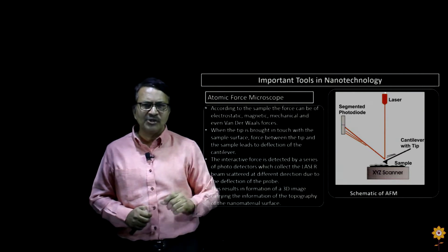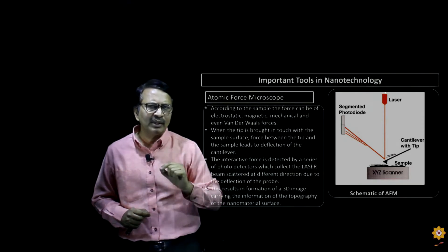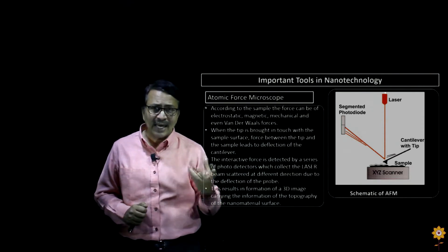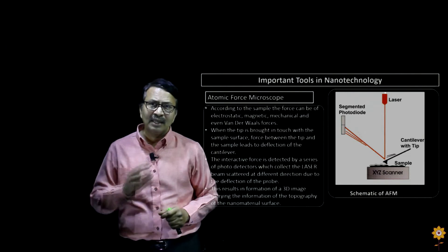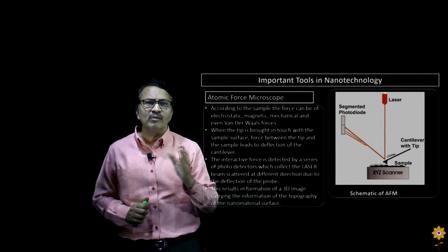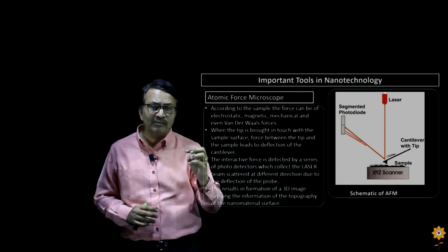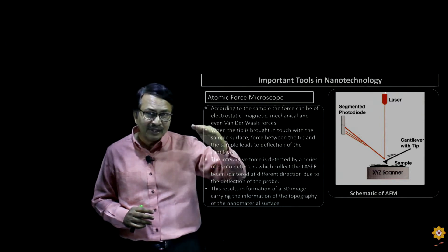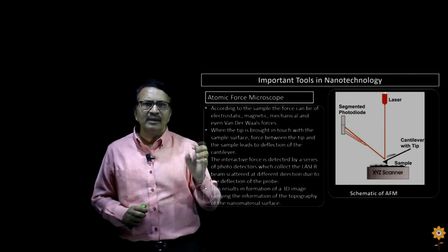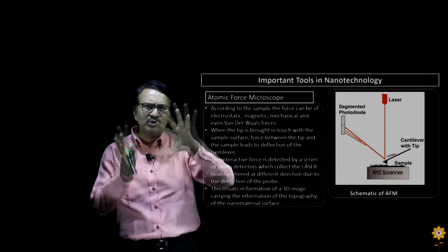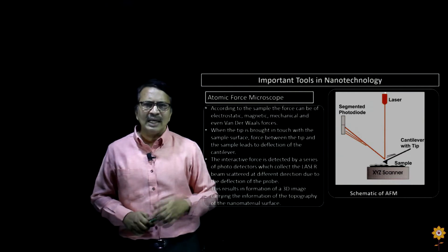One important thing to mention here: the interactive forces that exist between the sample and the tip of the cantilever. These interactive forces can be electrostatic, magnetic, mechanical, or Van der Waals forces. Depending upon the quantity of these forces, the deflection of the cantilever will change accordingly. This deflection is registered by the photodiode and ultimately projected as a 3D image of the surface. This is basically how an AFM functions.